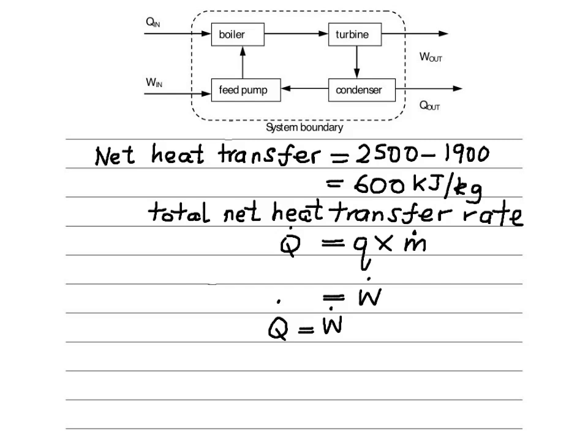So now we know W dot can be calculated as 896 kilowatts. Remember, 900 comes out but we have to put 4 kilowatts to drive the steam back to the boiler. So the net work is 896 kilowatts.